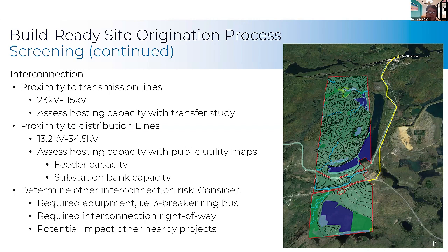In addition, most utilities in New York State require costly protection equipment known as the 3-breaker ring bus for a utility-scale solar project. The 3-breaker ring bus can essentially be thought of as a substation built exclusively to safely connect the project to the transmission system, and may cost the project developer up to tens of millions of dollars just by itself. Furthermore, projects that require long interconnection distances or require easements across multiple third-party landowners to reach a line are faced with additional burdens that could be costly and time-consuming to negotiate through.